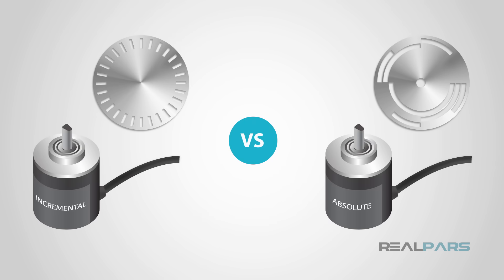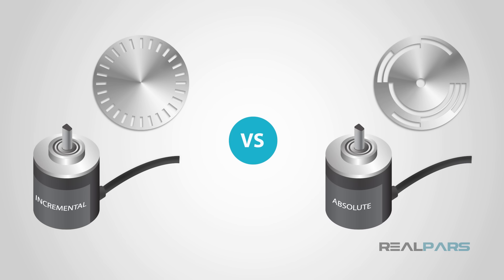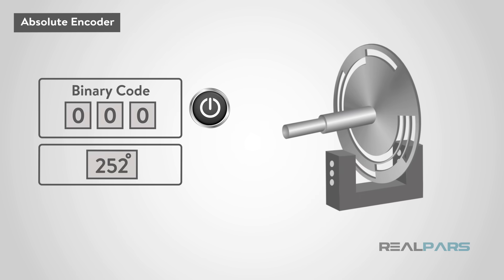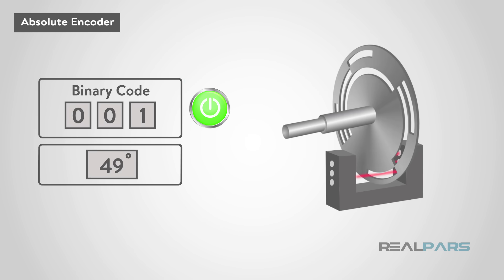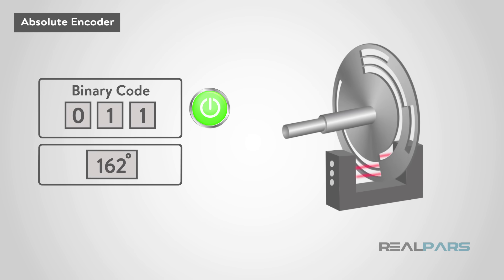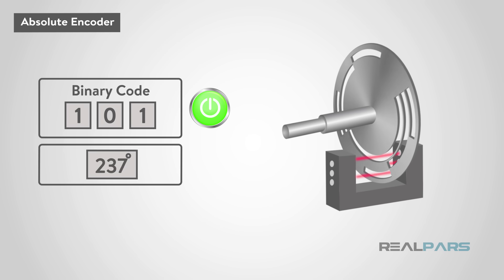Now that we have broken down the main groups, let's discuss the difference between absolute and incremental measurements, using the rotary encoder type as an example. In a rotary absolute measurement type encoder, a slotted disk on a shaft is used in conjunction with a stationary pickup device. When the shaft rotates, a unique code pattern is produced. This means that each position of the shaft has a pattern, and this pattern is used to determine the exact position.